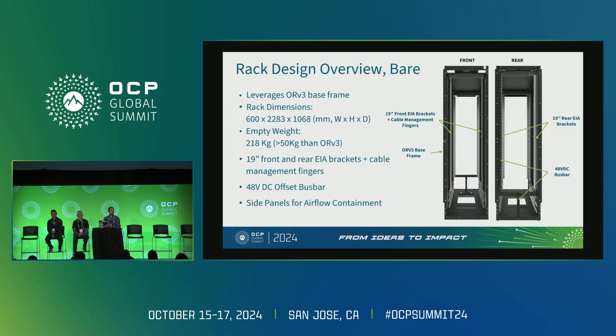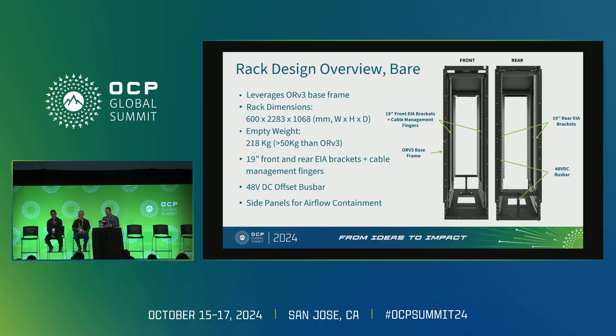Here's a look at the rack design overview at the bare metal. We leveraged the majority of the ORV3 base frame, with some modifications to the canopy. The rack dimensions are 600 mm wide by 2,283 mm tall and 1,068 mm deep. It weighs approximately 218 kg, which is approximately 50 kg heavier than the ORV3. We bolted on 21-inch to 19-inch adapter brackets to install network gear without needing additional shelves and trays. In the rear, we added a 48-volt offset bus bar. Side panel containment comes directly with the rack, whereas in traditional ORV3 those only come as an accessory installed at the end of rows.